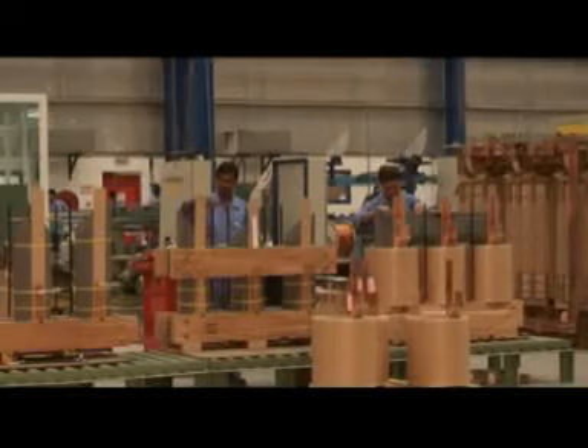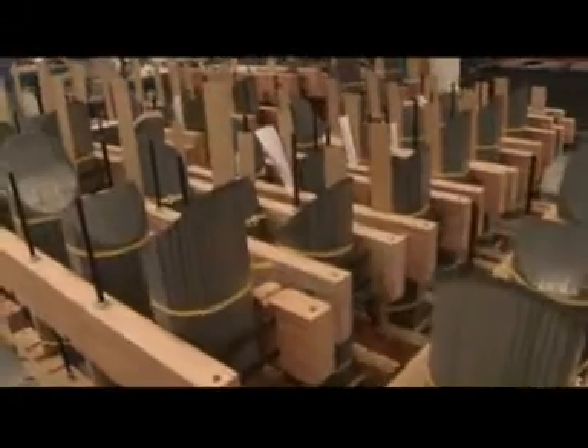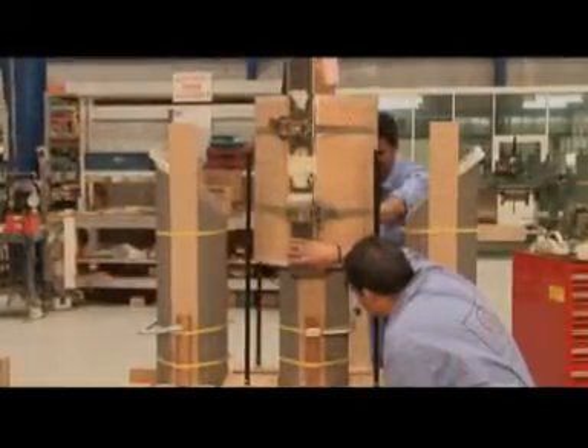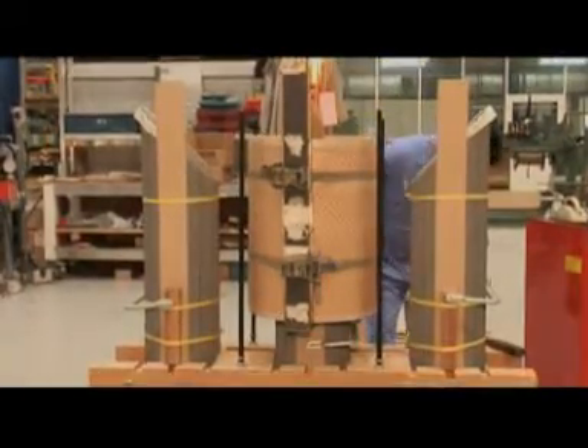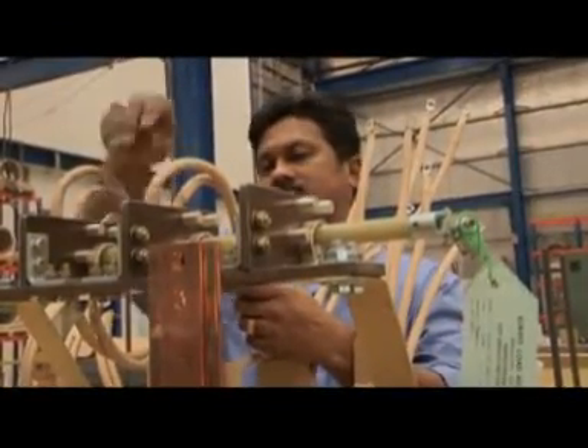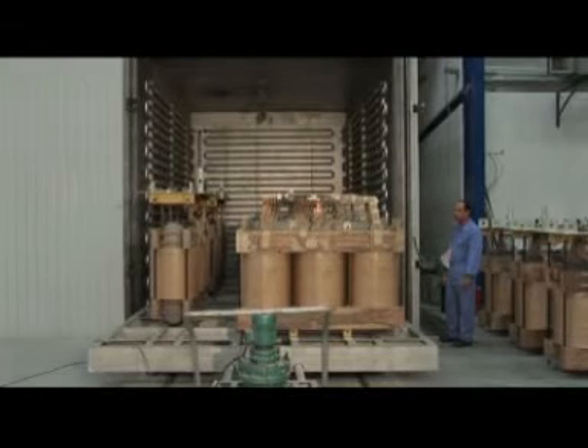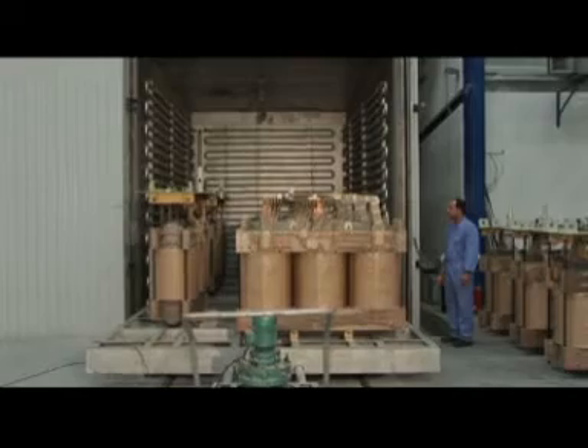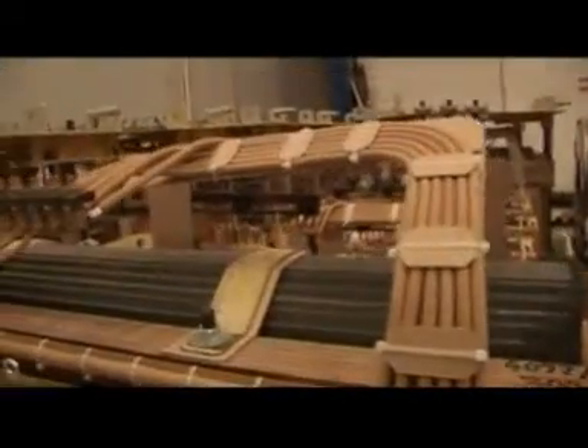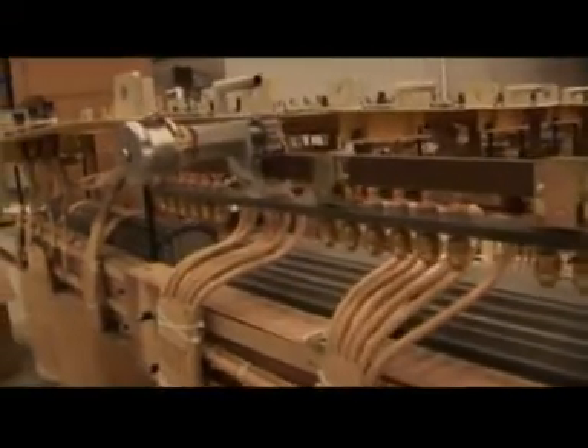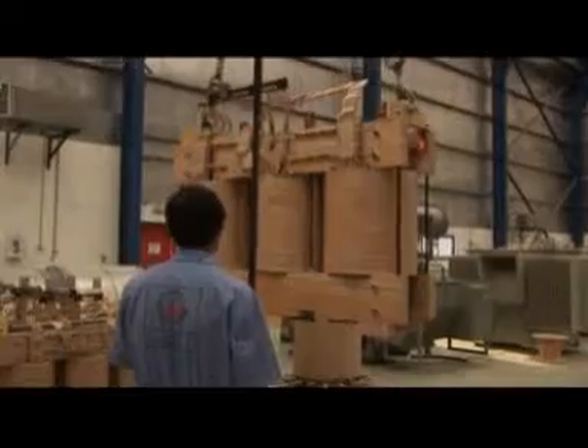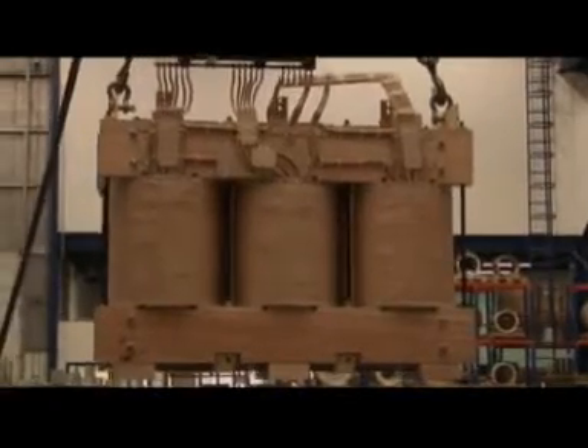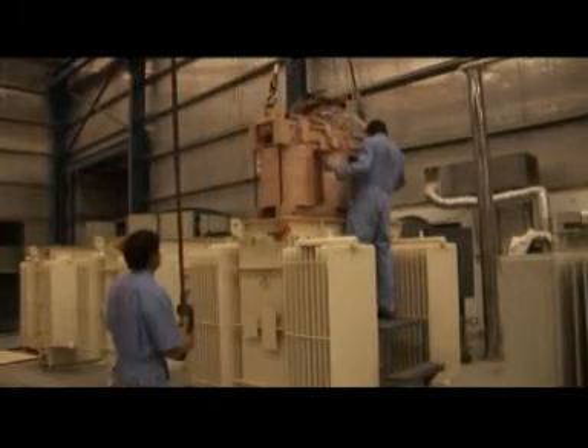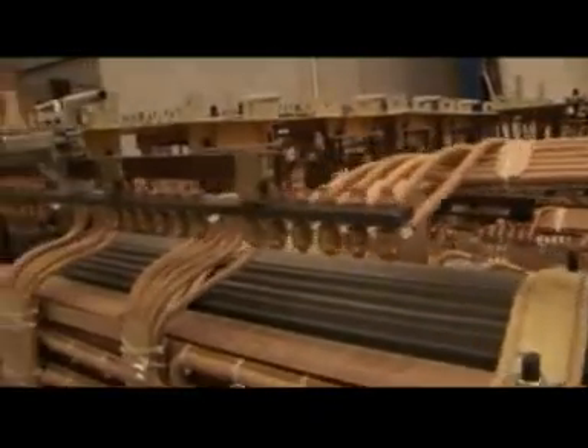The LV and HV windings are assembled concentrically on a three-limbed core. The top yoke of the core is assembled after the coils, and insulation supporters are assembled in place. The top frame is fixed, and the yoke clamp tightened properly after all the assembly processes. The drying process is carried out in a completely computer-controlled vacuum drying chamber, especially designed and built to ensure top-class quality of the product. A combination of heating and vacuum cycles removes any moisture from the active parts, ensuring flawless insulation. After the drying process, the active part is lowered inside a suitably designed and fabricated tank, and LV and HV connections are made to the terminals.